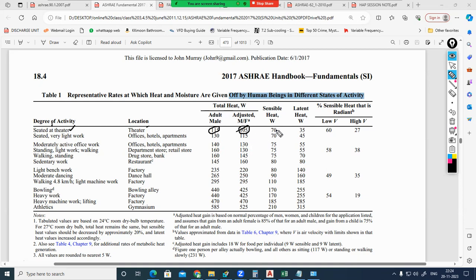Out of 105, 70 percent is sensible. So it means 70 watt is sensible, 35 watt is latent. Sensible more, latent less. Out of 70 sensible, the percentage of sensible heat means radiant and convective heat. From the body, air will be traveling due to the air velocity, meaning air will be traveling through the surface. So accordingly, convective heat with respect to the air velocity, the heat that is ejecting from the human body to the surroundings, is convective.